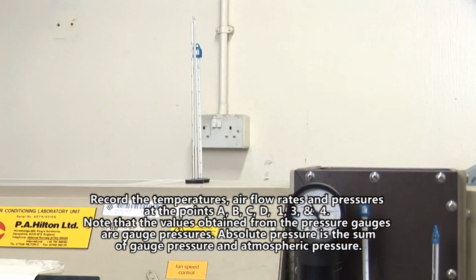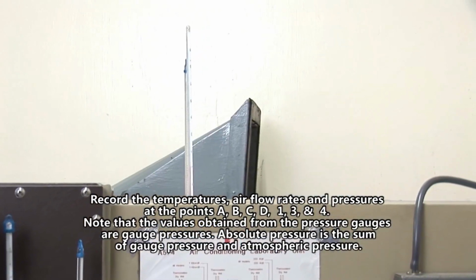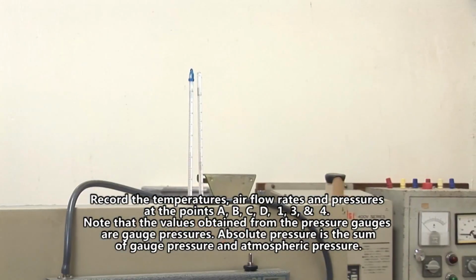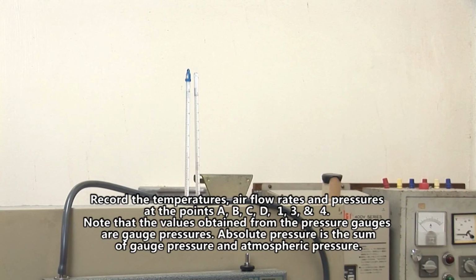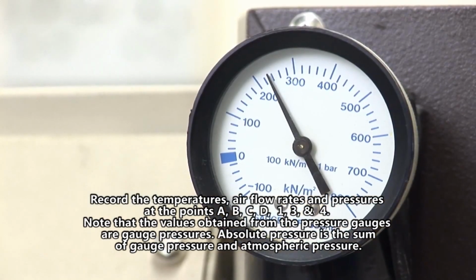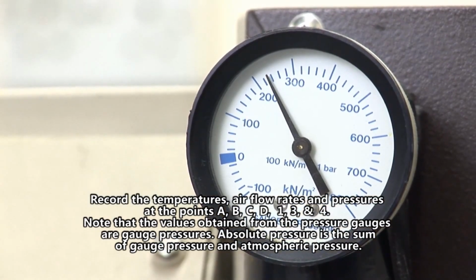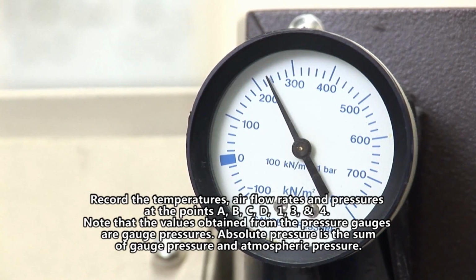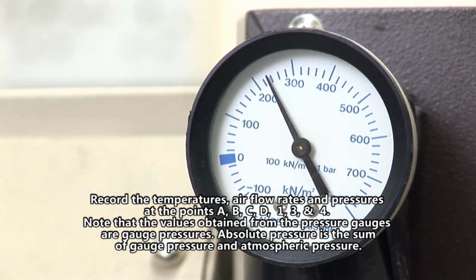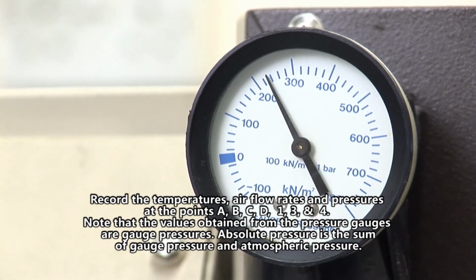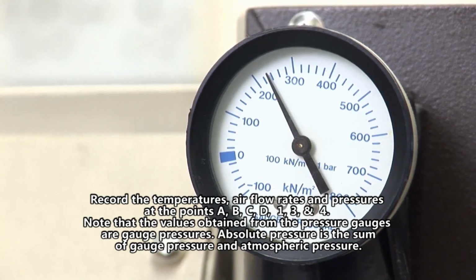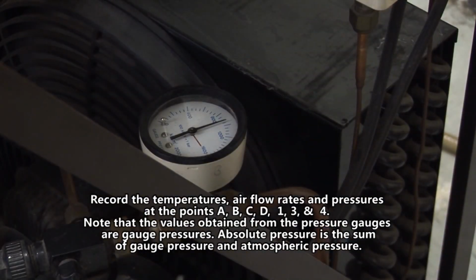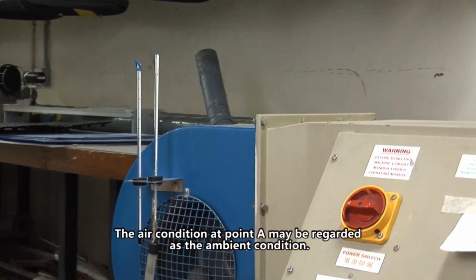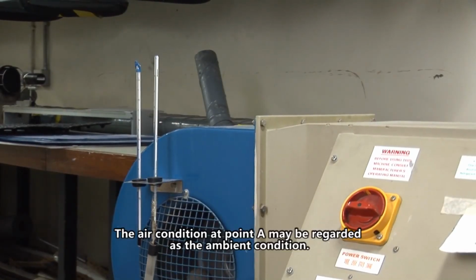This is the observation sheet provided in the lab manual. Record the temperatures, airflow rates and pressures at the points A, B, C, D, 1, 3 and 4. Note that the values obtained from the pressure gauges are gauge pressures. Absolute pressure is the sum of gauge pressure and atmospheric pressure.